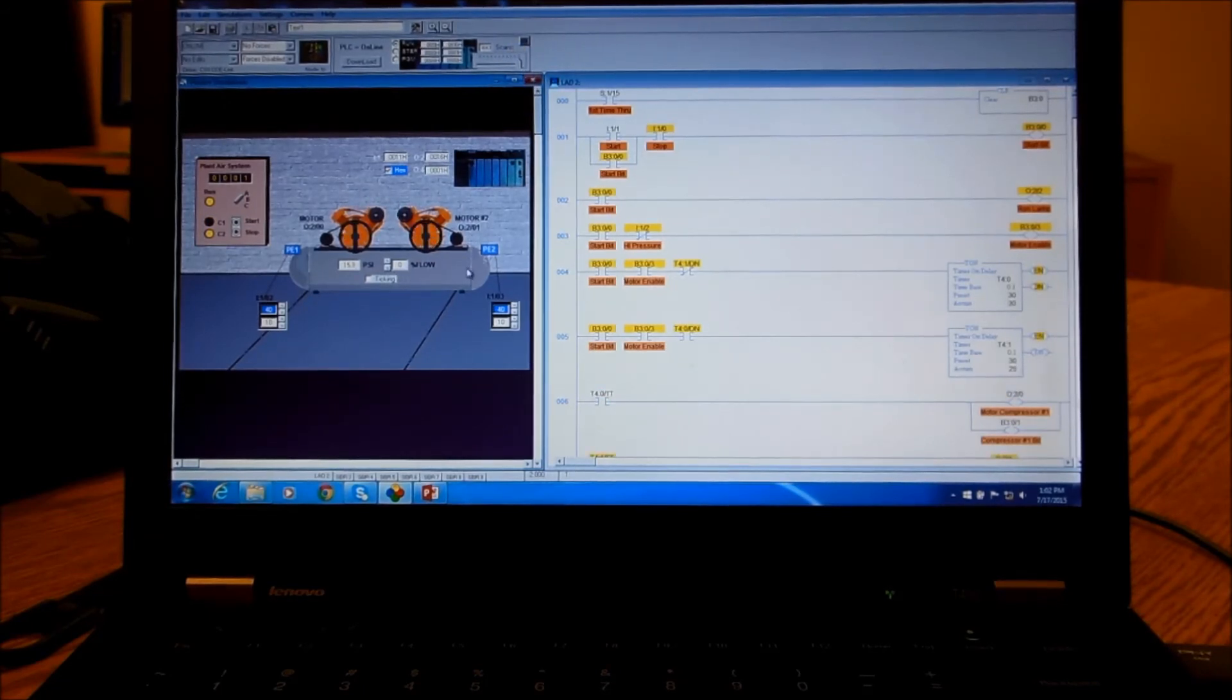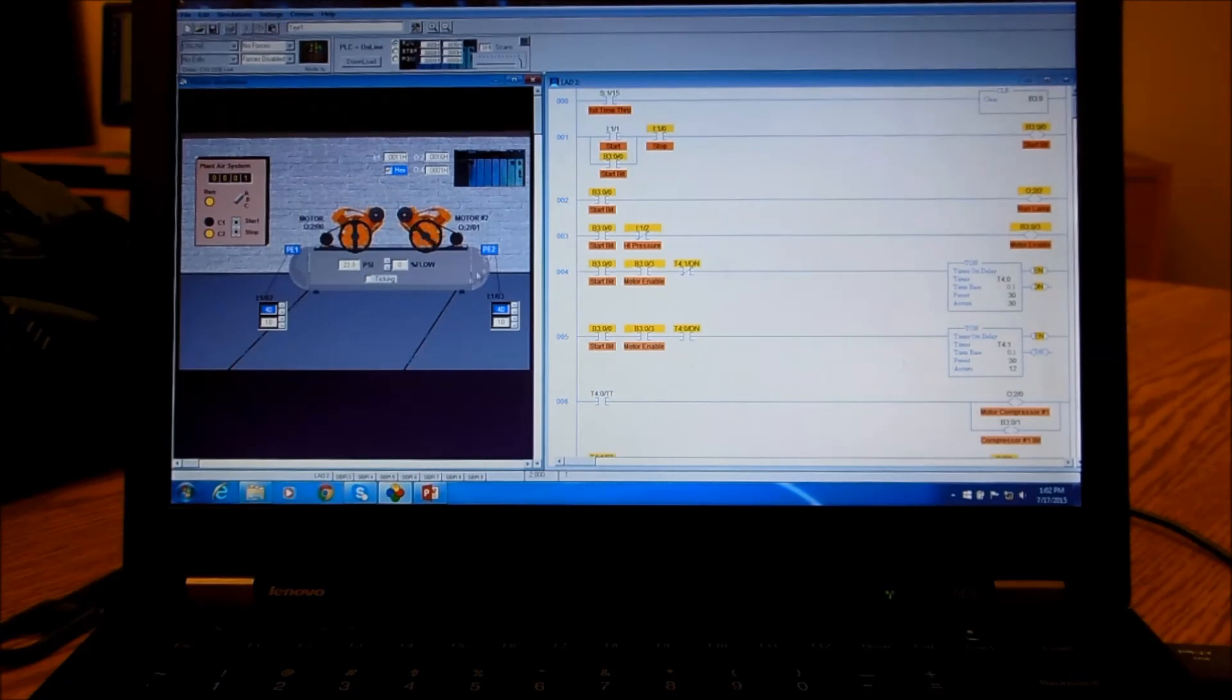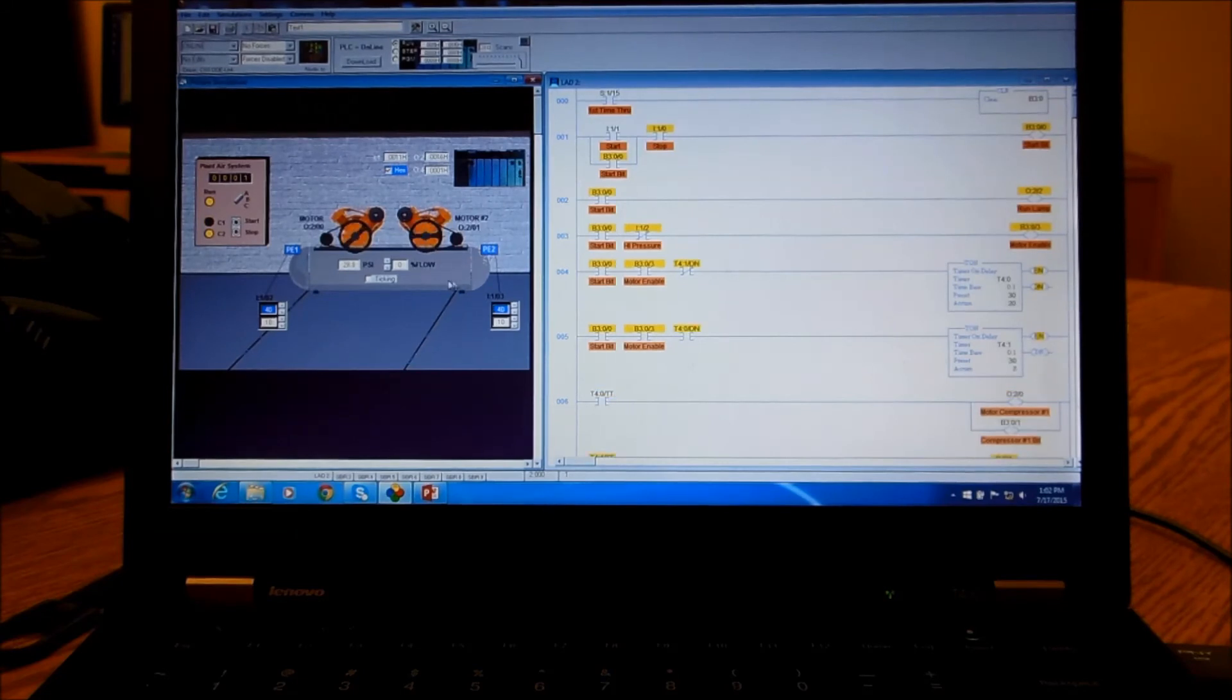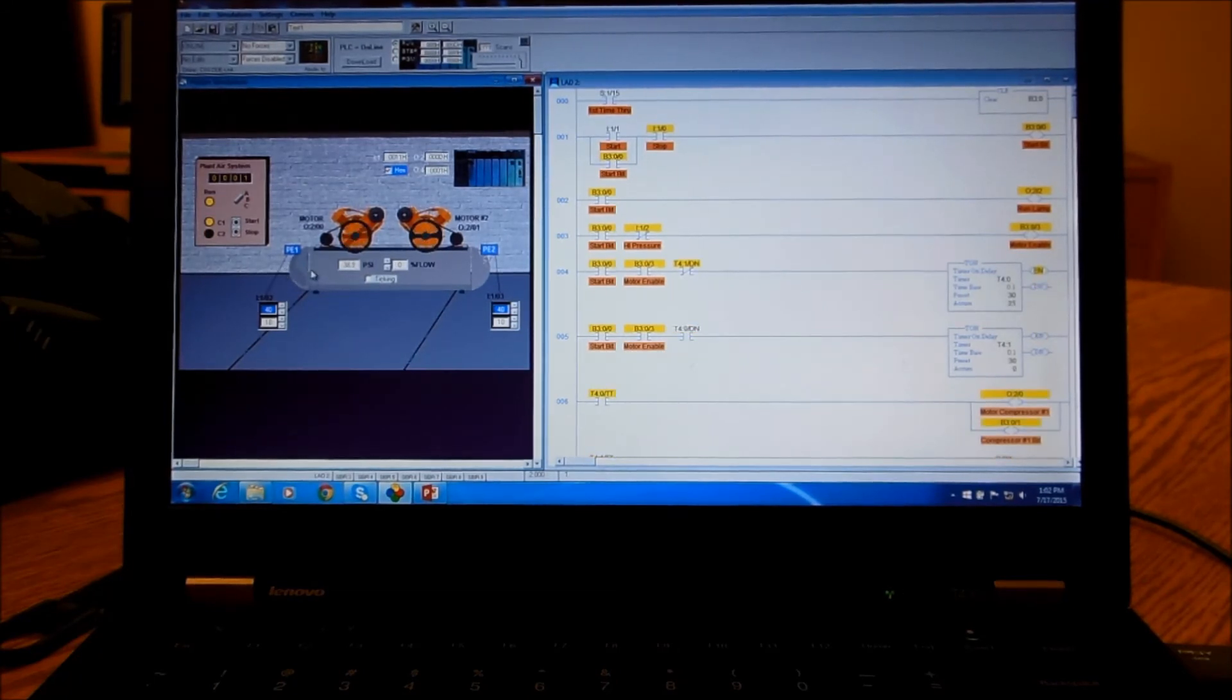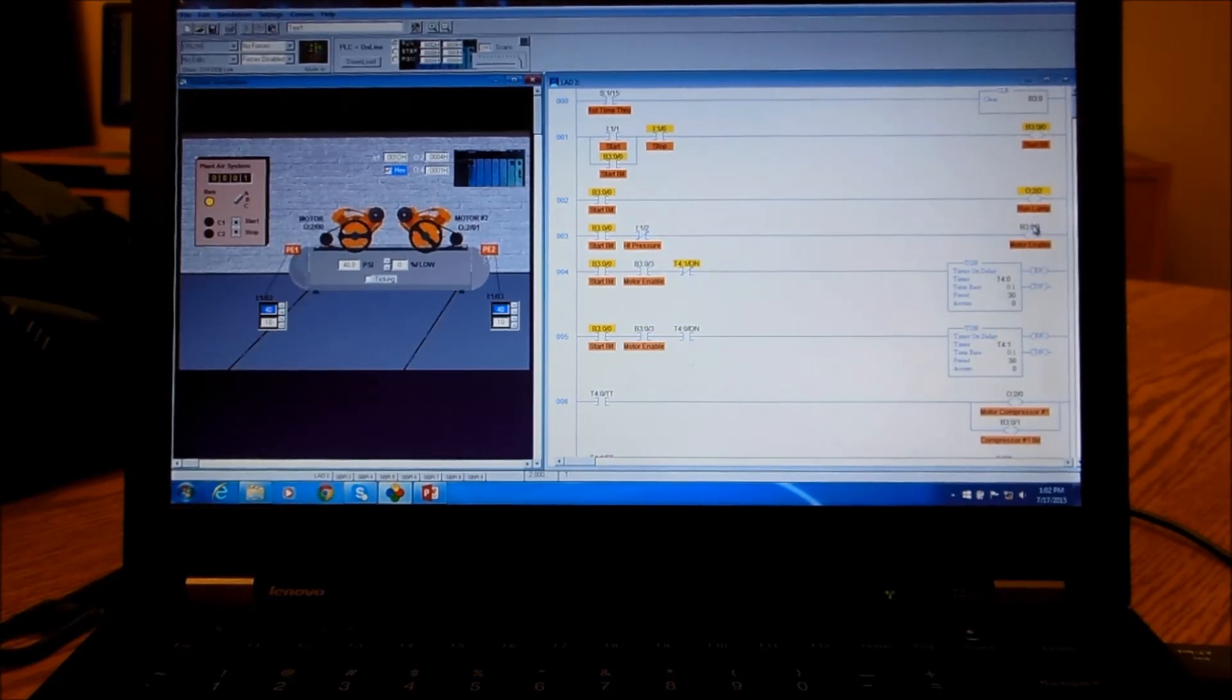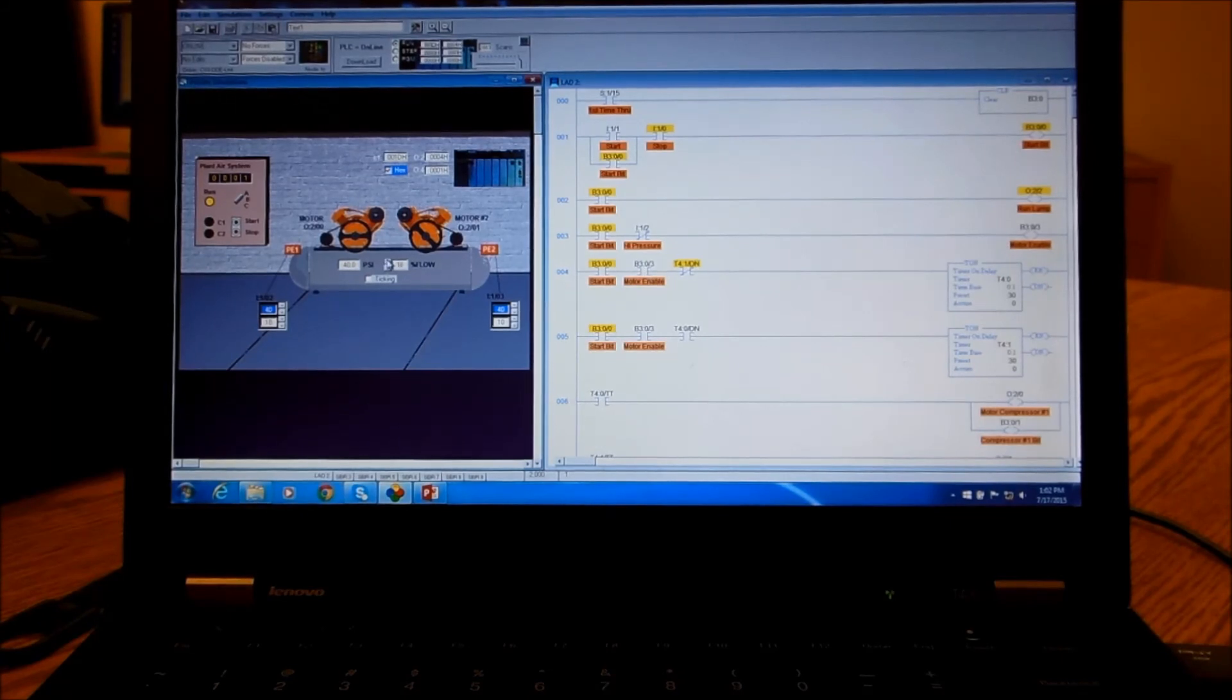That is basically what percentage of it leaks out of the system. So when we're pressurizing it we want it to be at zero. When we're emptying the tank or relieving the pressure we want to put this at like 100. We're almost at the end of a cycle here, and when we get to 40 it'll shut off. That'll be signified by this bit and that turns off our motor enable signal over here. What we'll do is to get it to drain faster, we'll put this up to a high value.